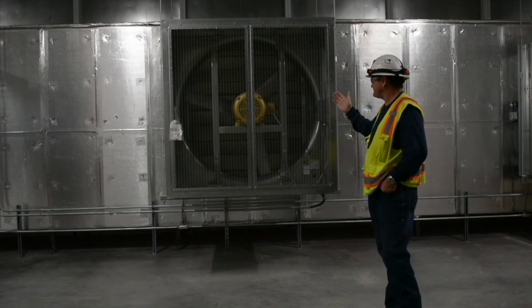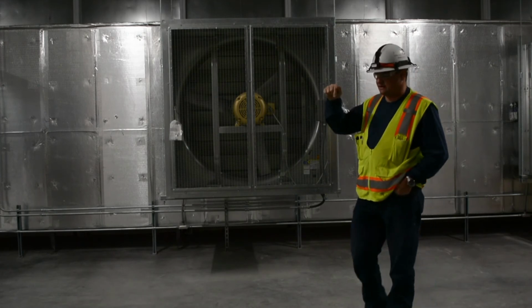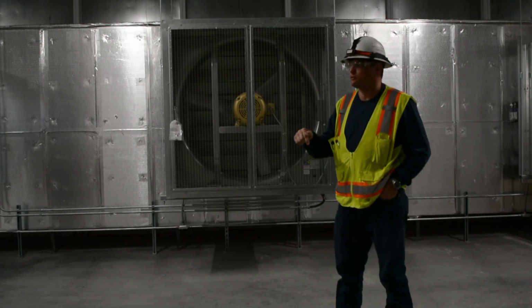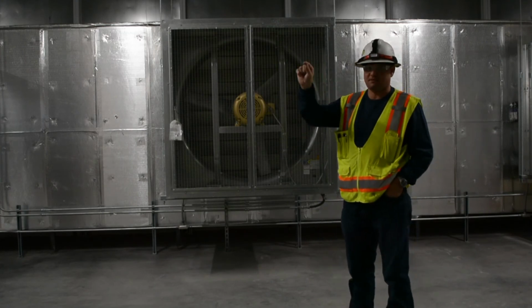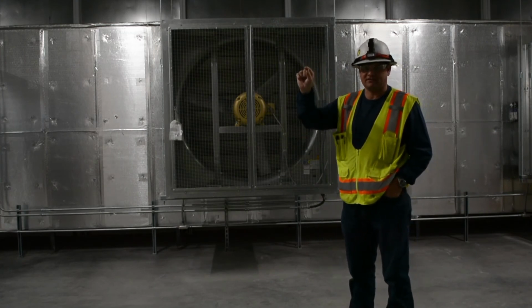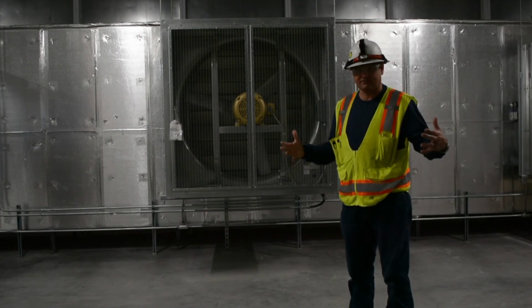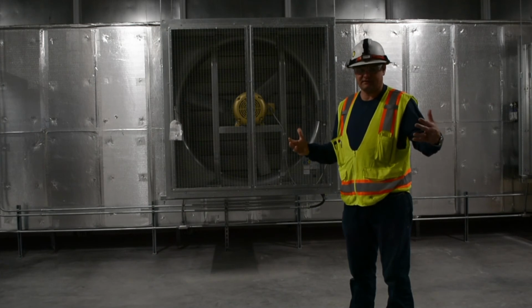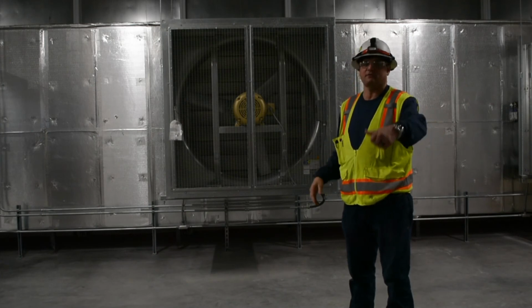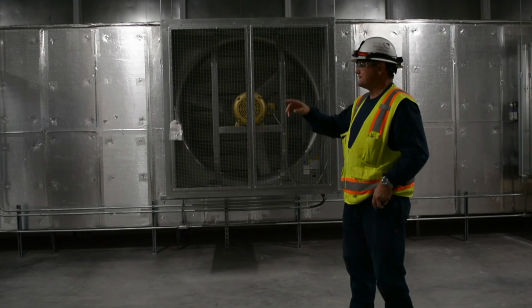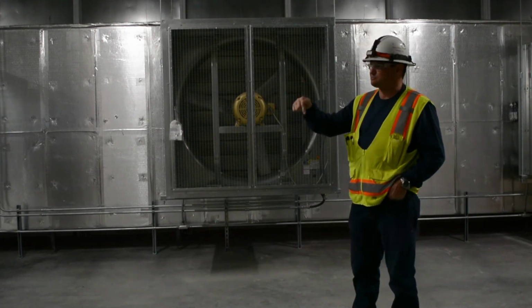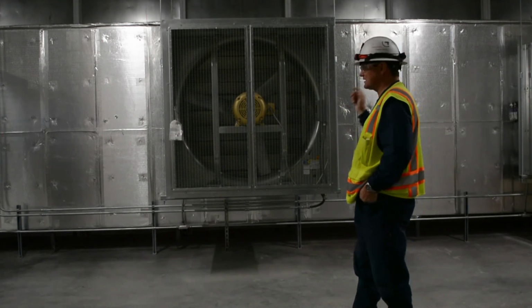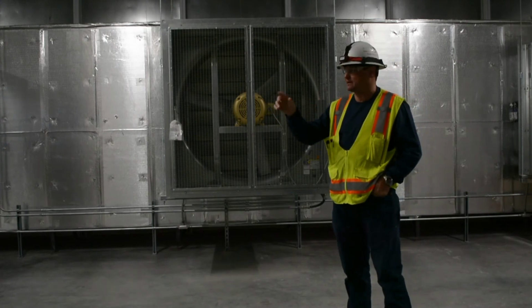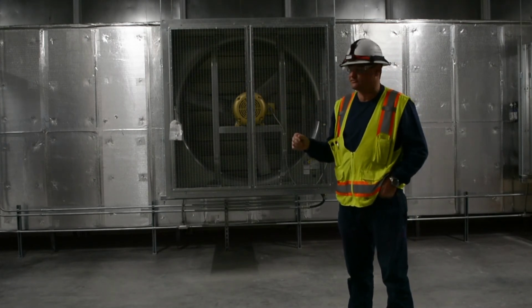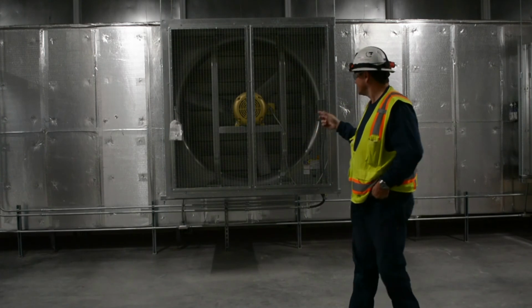These fans will come on to maintain space pressure on the 5th floor anytime we're in economizer of the main air handling systems, and the relief air is going into this floor for conditioning purposes, as well as giving it a site for relief dump of the quantity of air that we're trying to relieve. These fans will monitor the space pressure and stage up one at a time in order to maintain that pressure and modulate with their variable frequency drives to do such as well.